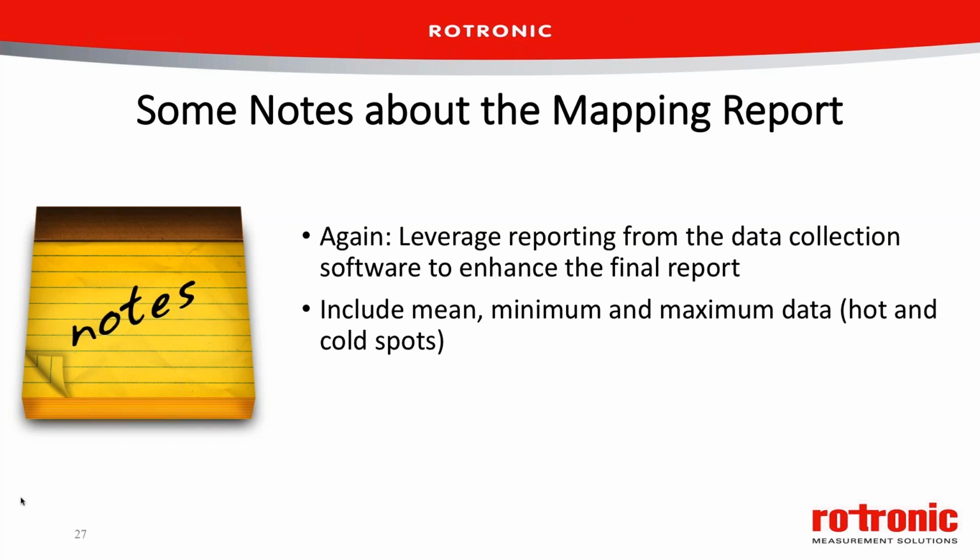And these figures can be compared between all the logger locations within the space. This enables the analyst to identify the locations where the mean temperatures are consistently low or higher, an outcome that cannot be achieved simply by comparing individual data points.